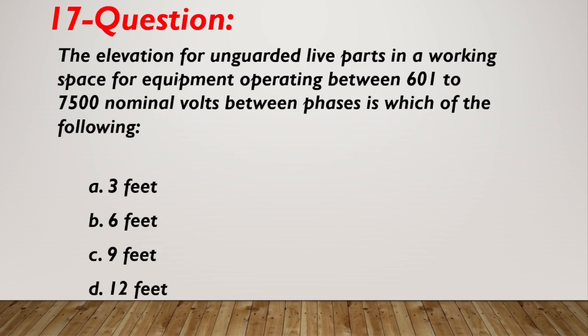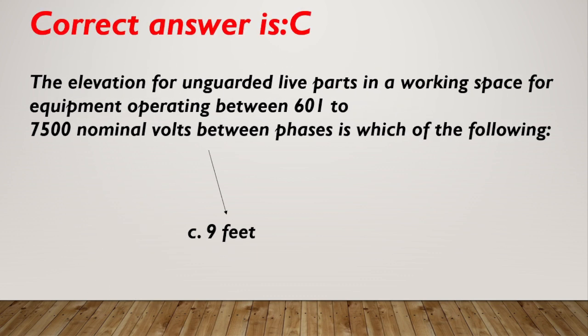Question number 17. The elevation for unguarded live parts in a working space for equipment operating between 601 to 7,500 nominal volts between phases is which of the following? A. 3 feet. B. 6 feet. C. 9 feet. D. 12 feet. Correct answer is C, 9 feet.